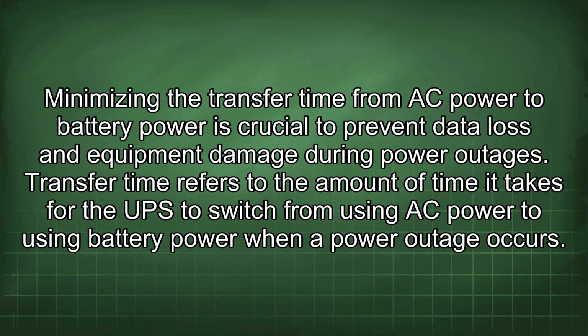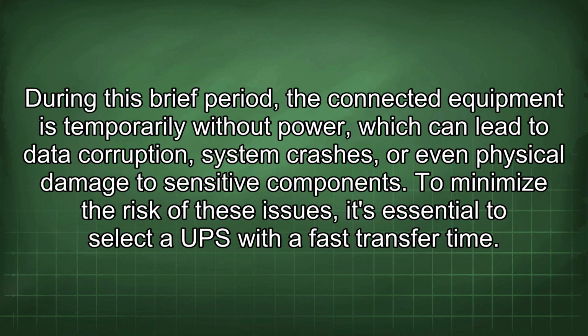Minimizing the transfer time from AC power to battery power is crucial to prevent data loss and equipment damage during power outages. Transfer time refers to the amount of time it takes for the UPS to switch from using AC power to using battery power when a power outage occurs. During this brief period, the connected equipment is temporarily without power, which can lead to data corruption, system crashes, or even physical damage to sensitive components.